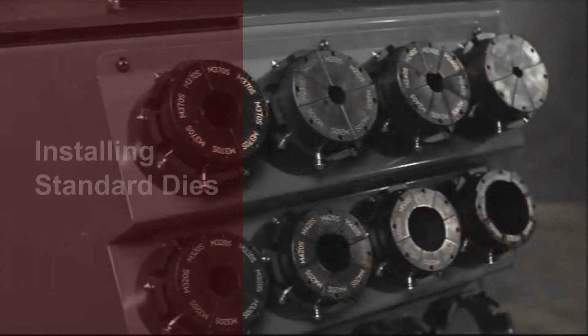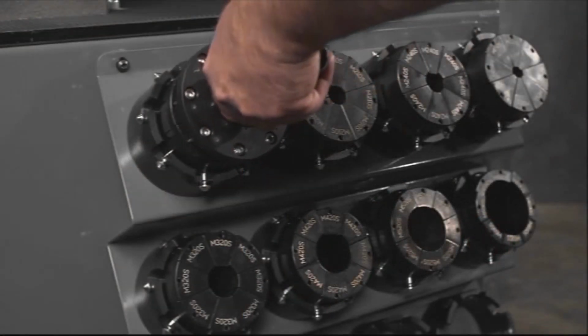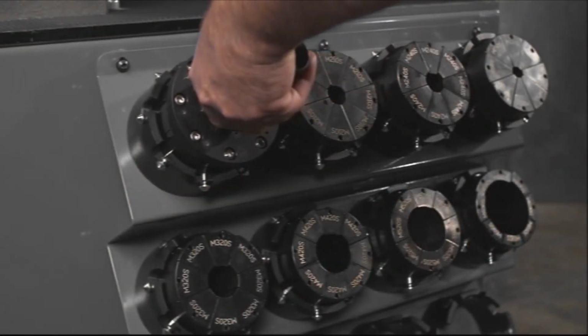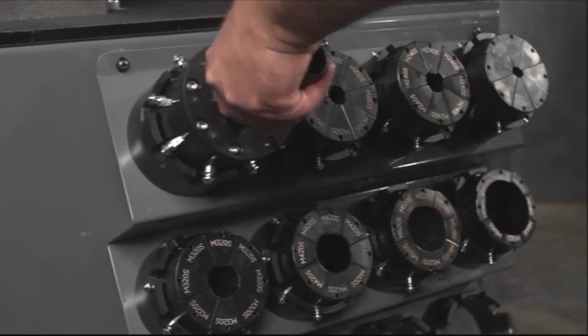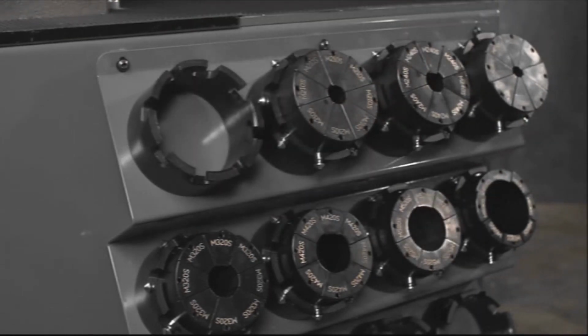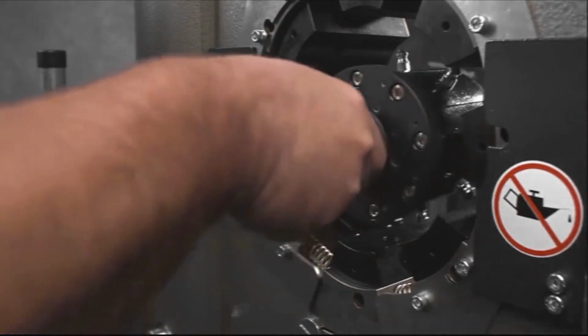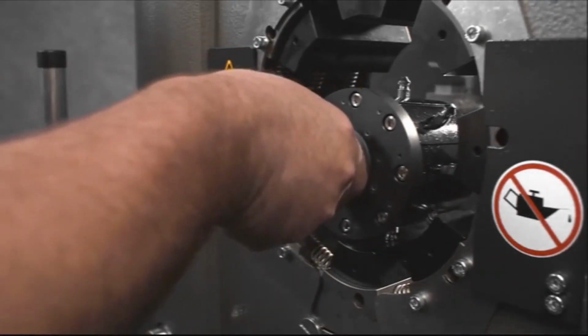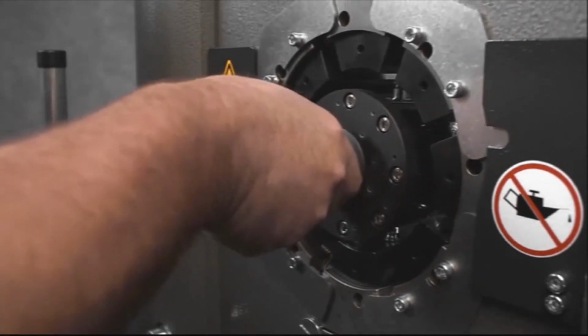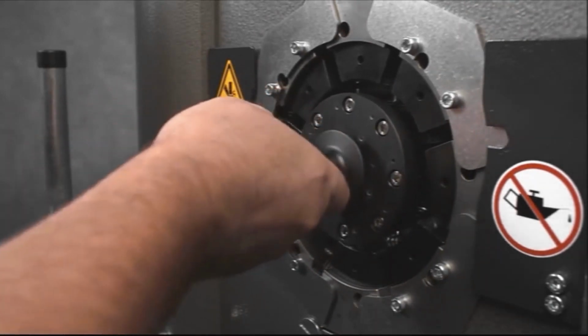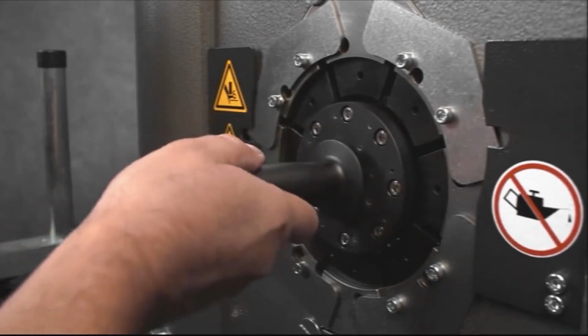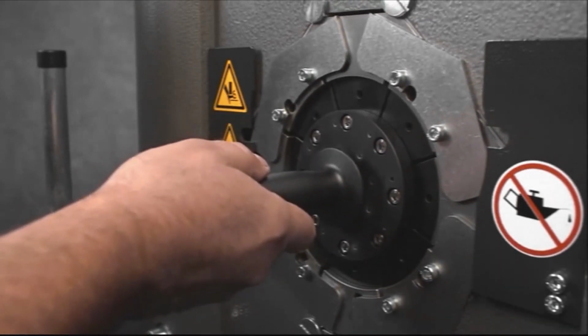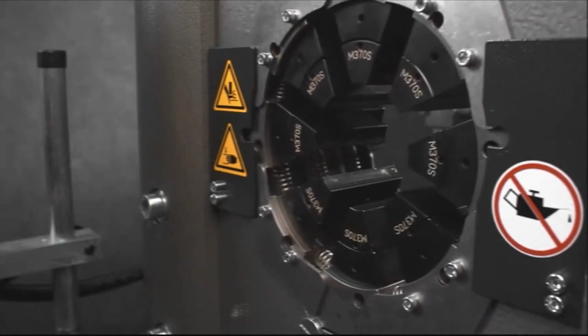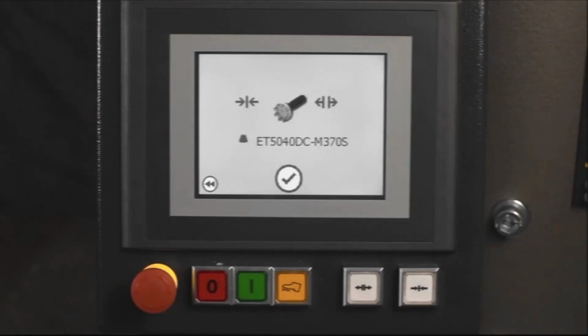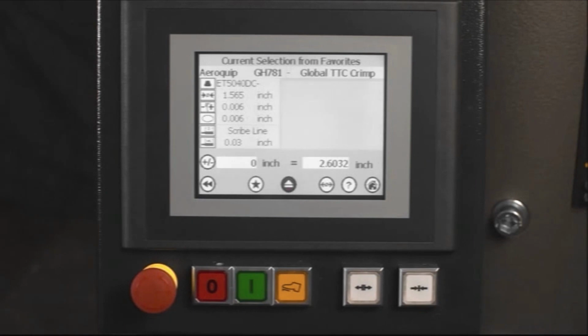Align and insert the 8 pins of the QDC tool with the holes in front of the desired crimp dies in the storage rack. Rotate the handle clockwise and remove the desired standard dies from the storage rack. Position the QDC tool with the standard dies in the center of the crimp head. Make sure the holding pins are aligned with the bore holes in the adapter dies and gradually close the crimp head while confirming all 8 pins are aligned. Remove the QDC tool and retract the crimp head. Confirm the standard dies are secure. Then press the check button to acknowledge installation of correct tooling for the application.